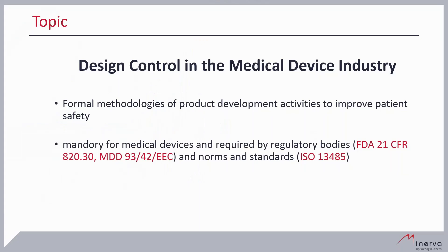Thank you very much, Thomas, for that introduction. Today's topic is design control in the medical device industry. Design control is related to the product development process of a medical device and is the formal methodology to improve patient safety. That means every medical device manufacturer needs to integrate structured activities into the design process.